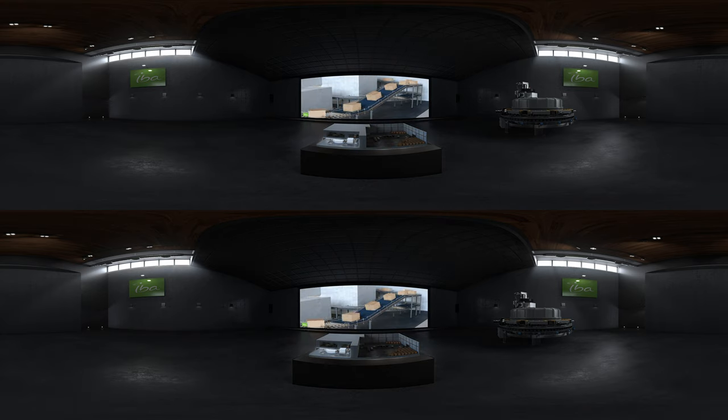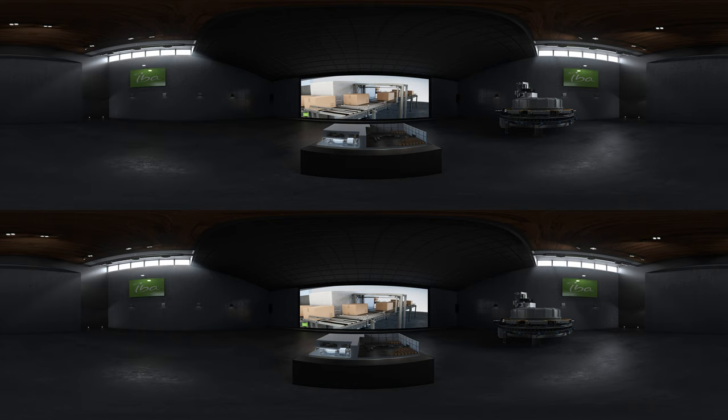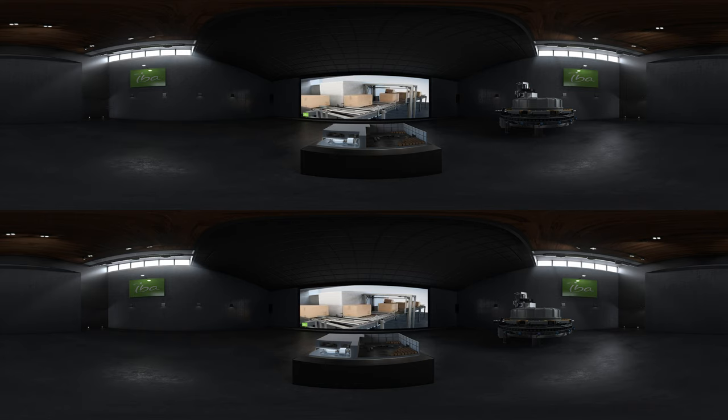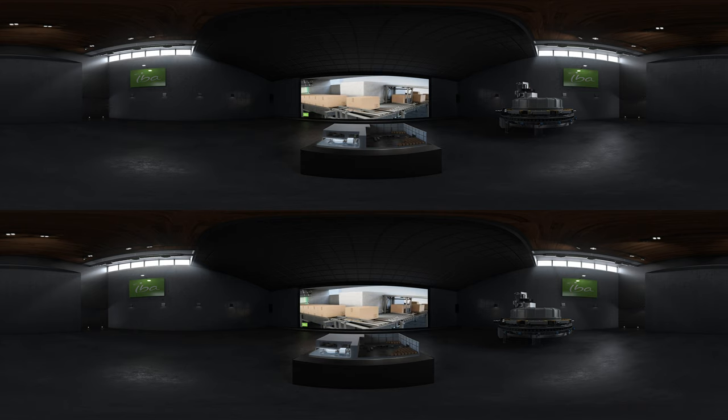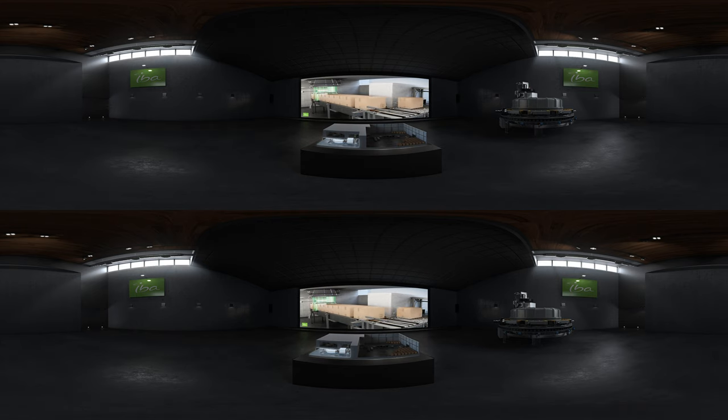The boxes are transported by the conveyor up to the irradiation section. The system avoids any gap between boxes so as to maximize the beam use. The boxes then pass through the electron curtain.